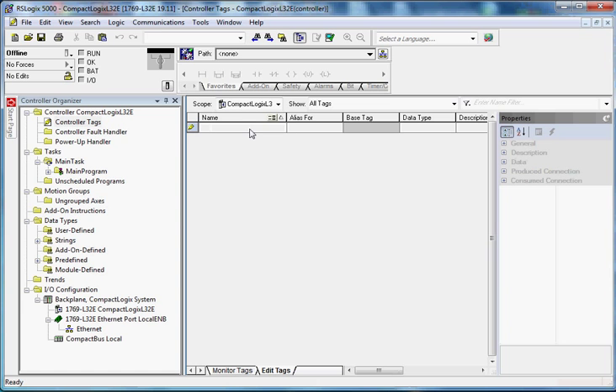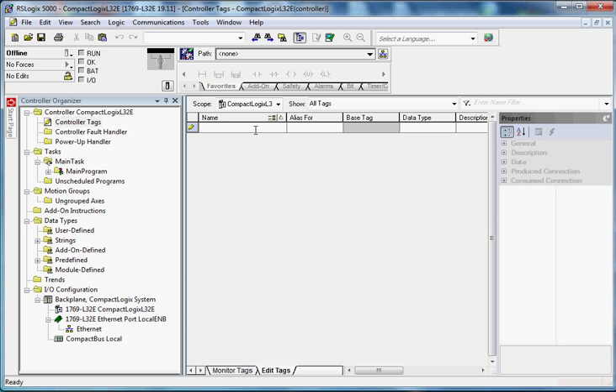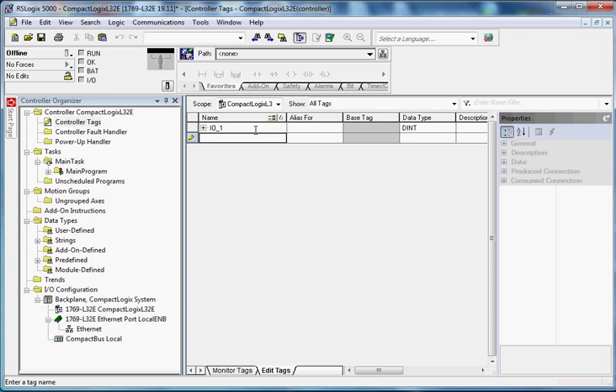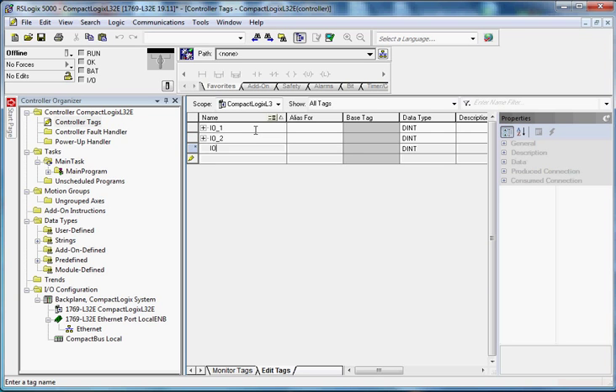So if I hit the edit tag button, and let's say in this example that I'd like to look at some input data, and I'd like to be able to turn on some outputs. Now, if you're familiar with the Banner wireless products, particularly the DX80 SureCross, generally you'll know that each device has 16 registers in it, of which the first eight generally are input data, and the next eight generally are output type data. So I'm going to put here, and they usually just, in the documentation from Banner, they basically just go IO1 all the way up to IO16. So I'm going to go ahead and create this first one, IO1, enter, and I'll go ahead and create another one, IO_2, IO_3, and I'll just do this for all of them.